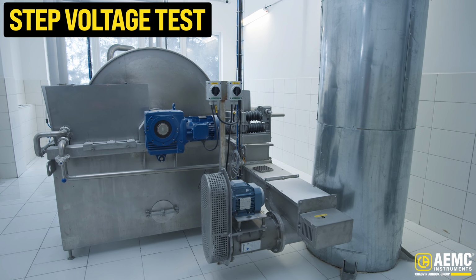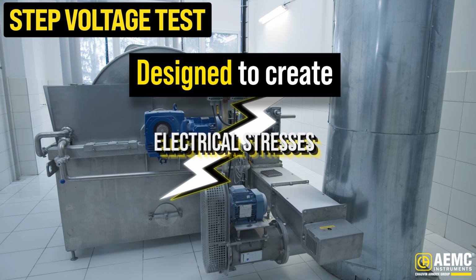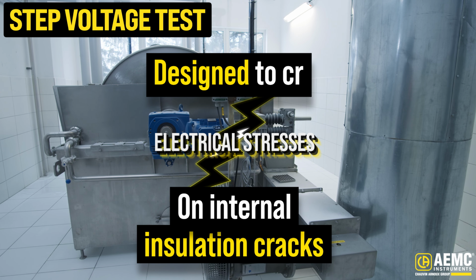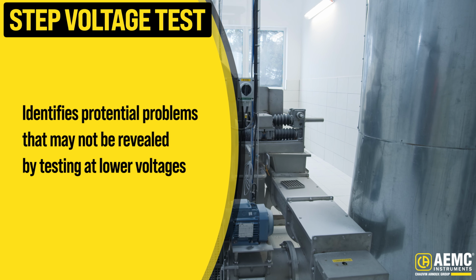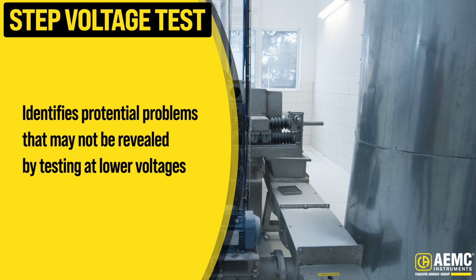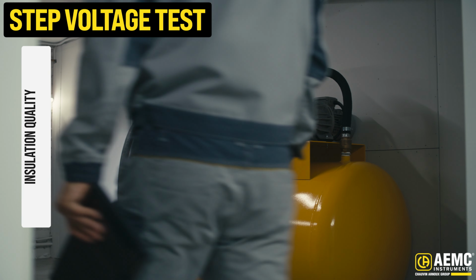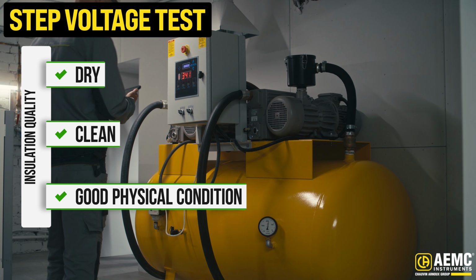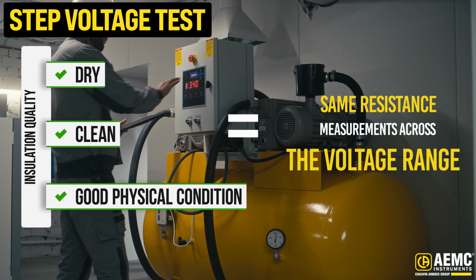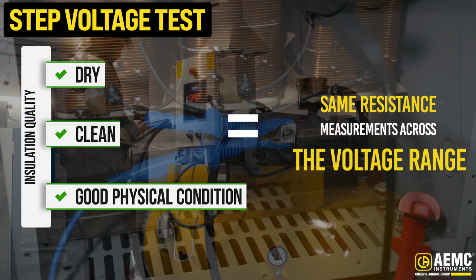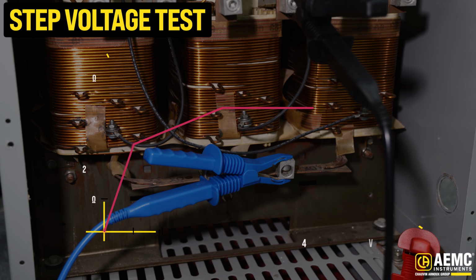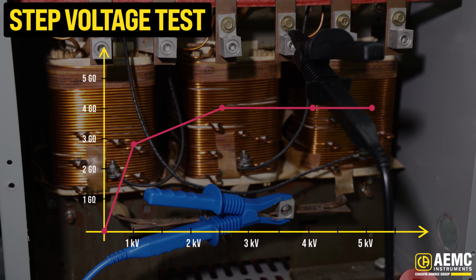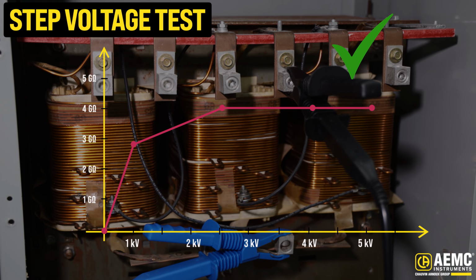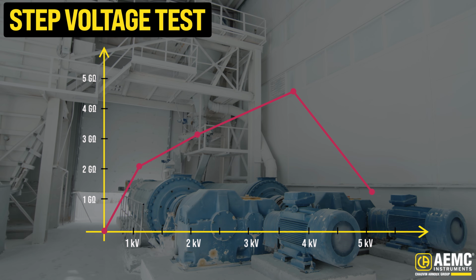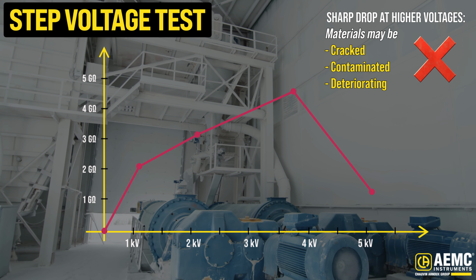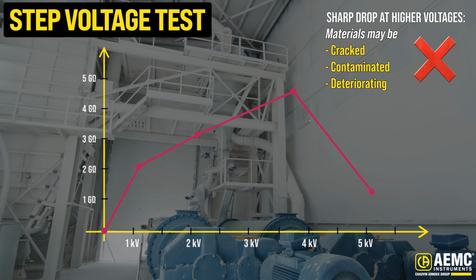The step voltage test is designed to create electrical stresses on internal insulation cracks, identifying potential problems that may not be revealed by testing at lower voltages. Insulation that is thoroughly dry, clean, and in good physical condition should provide roughly the same resistance measurements across the voltage range. If resistance stays consistent across voltage levels, insulation is in good shape. If it drops sharply at higher voltages, the material may be cracked, contaminated, or deteriorating.